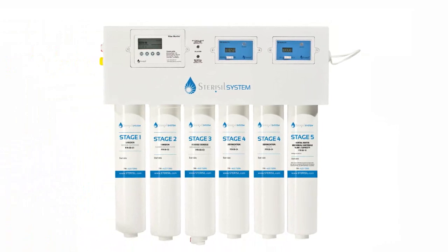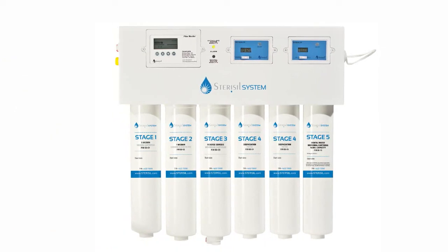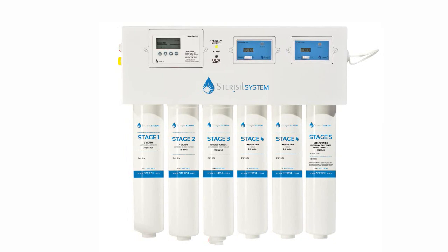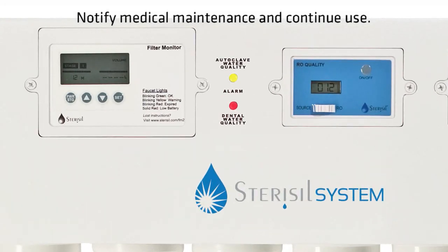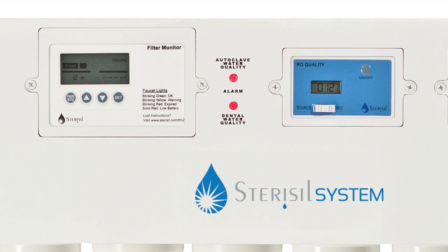The Sterisil system is designed to notify you with both visual and audible alarms when a cartridge is depleted. Please notify medical maintenance or a Sterisil system certified technician should any of the LEDs on the faceplate turn red or a loud beeping is coming from the system, as these indicate that specific cartridges have reached the end of their use and are ready to be replaced. If a certified technician cannot be reached, please call Sterisil Technical Support at 719-622-7200 or email support@stericil.com.